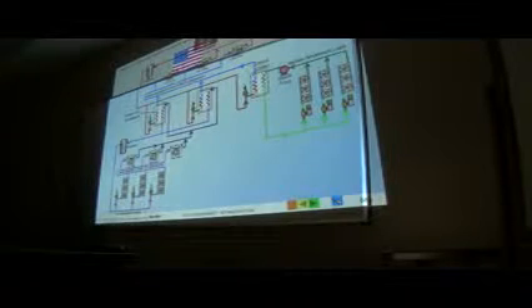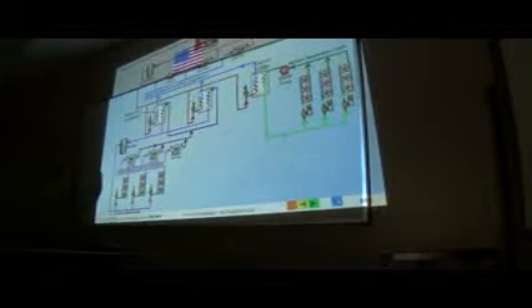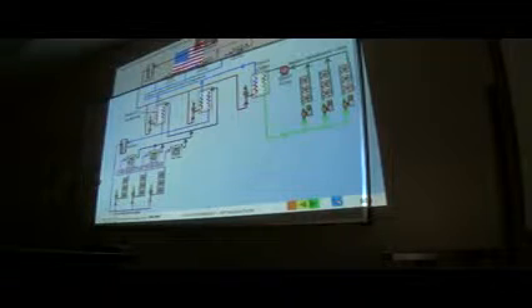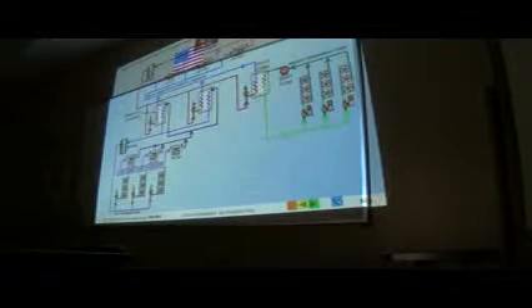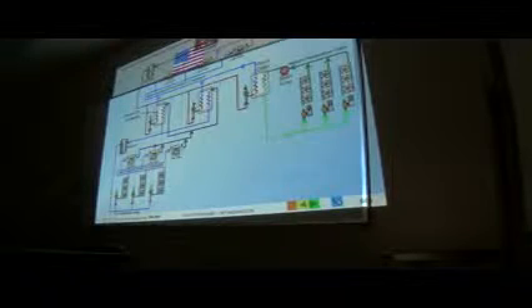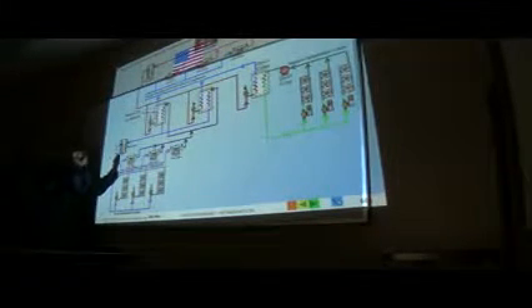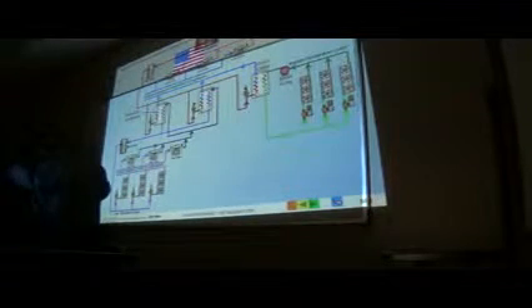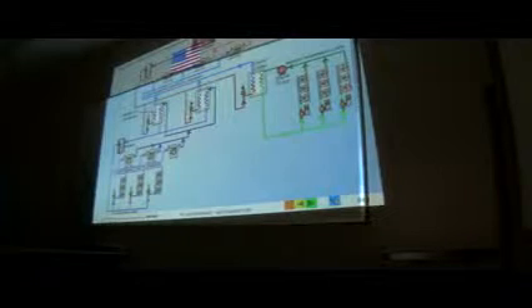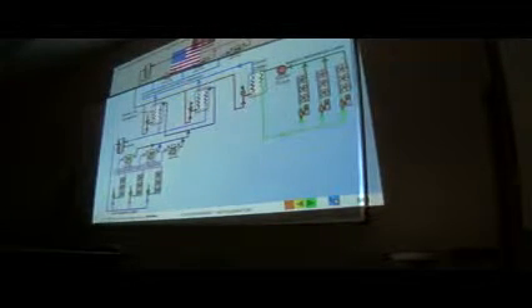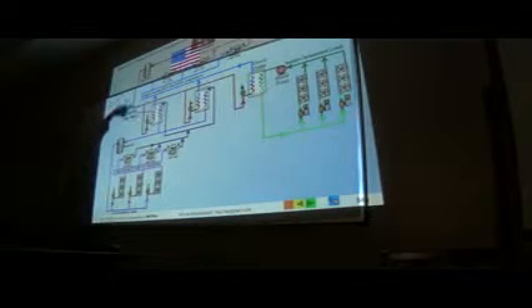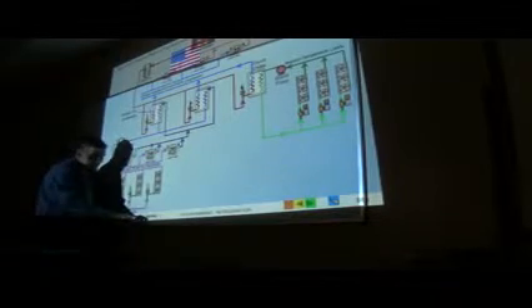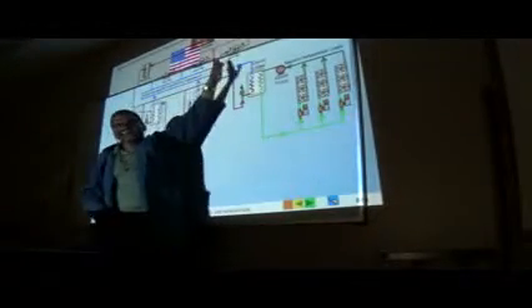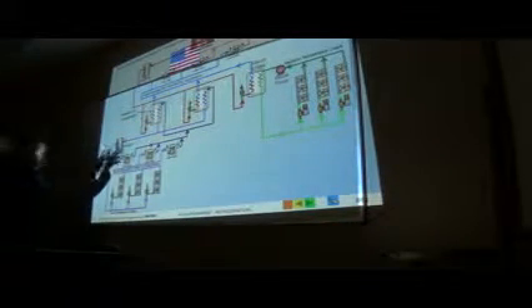Should we cover the cascade system? The only place you'll see a cascade system is when we need to go down to very low temperatures, say negative 120 degrees, like for science, frozen animal or disease control work. A regular compressor can't handle negative 120 suction while also handling the head pressure needed to condense the refrigerant, because the suction would be way down low and the discharge way up high. So instead we use three different systems.